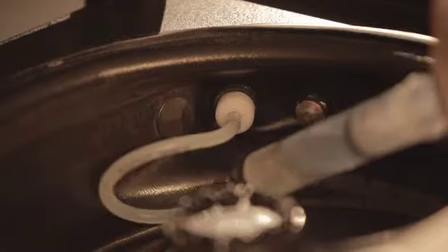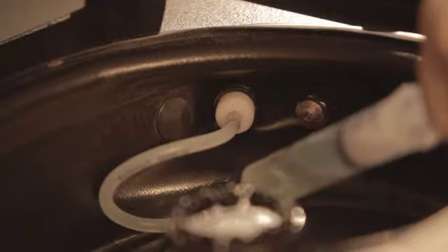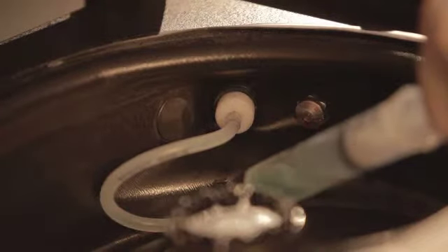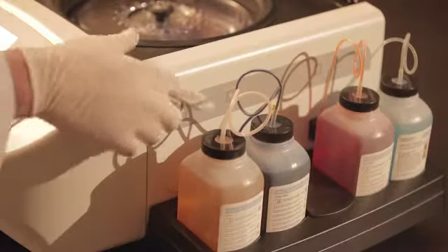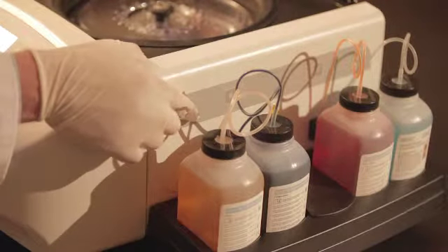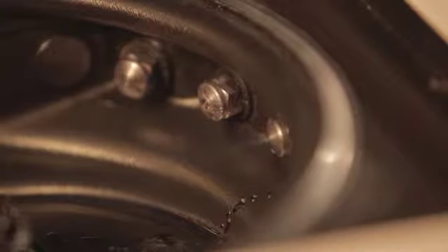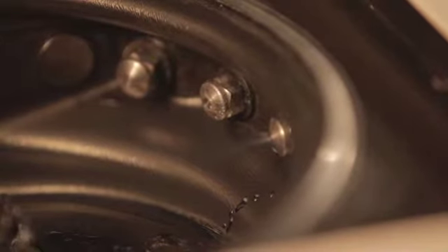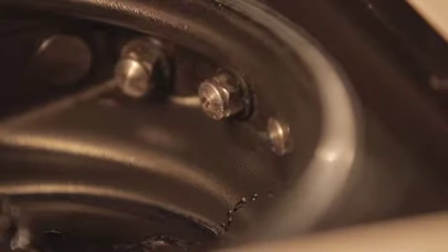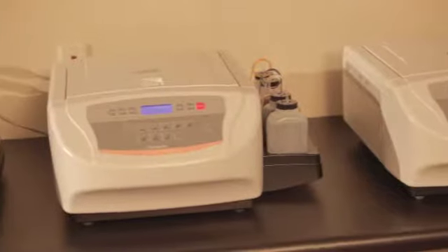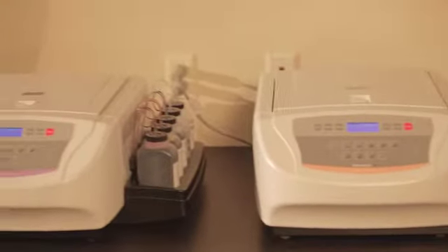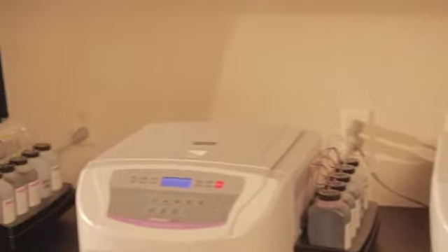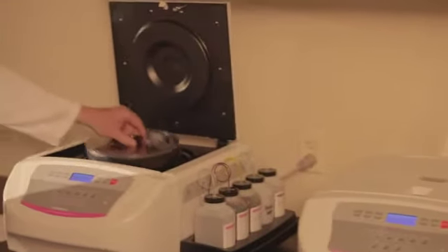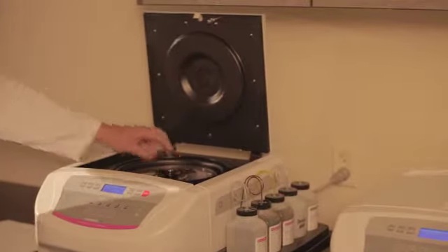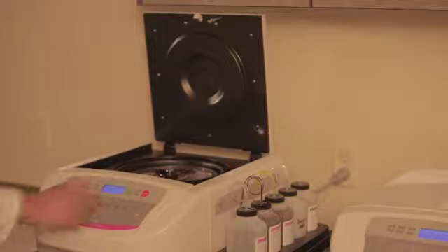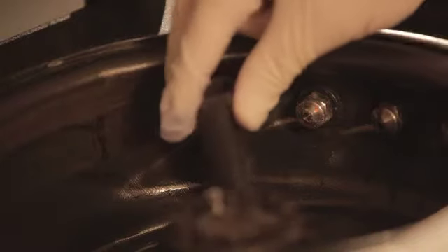This tool is also used when a stain bottle is completely emptied and the pump seizes. Even though you may begin to see the reagents sprayed from each nozzle, more priming is required. Stainers are shipped with alcohol in each line to keep the pumps lubricated and keep them from freezing. It is a requirement to pump at least 200 milliliters of stain through each line to remove all the alcohol in the pumps. This is done by first removing each nozzle.